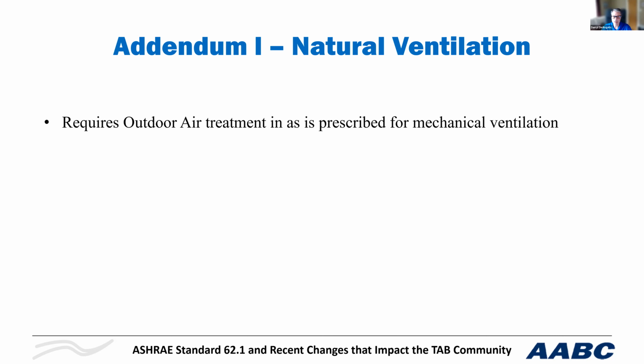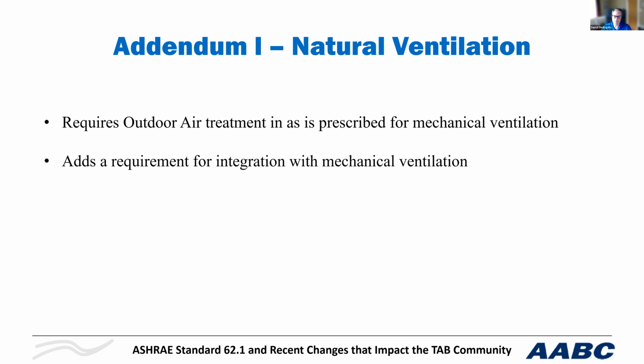And speaking of that, there is now a requirement for integration with mechanical ventilation. There are some exceptions to this. But why would you want to integrate with mechanical ventilation? Well, the wind doesn't always blow. In some areas it's very windy, maybe the Windy City or San Francisco and other places, but not 100% of the time. So you may not have the pressure forces needed to get the right ventilation amount in there. And in other cases, openings may be adjustable. If someone has the ability to close the opening, then obviously you're not going to get the right amount of fresh air. If they're variable, perhaps it's not at the right setting point that it should be. So you want to make sure that you're providing the same minimum ventilation, regardless of whether it's mechanical or natural. So we're going to start seeing more hybrid systems, and this should have more TAB involvement.